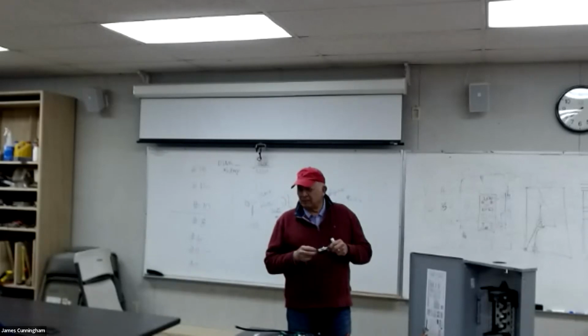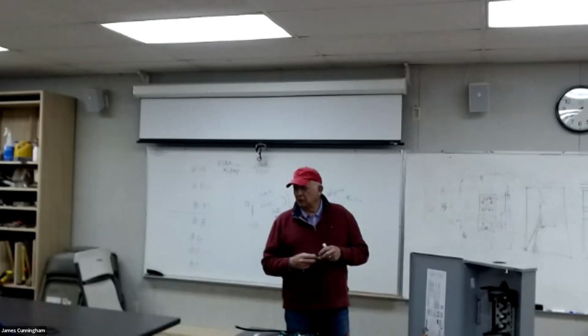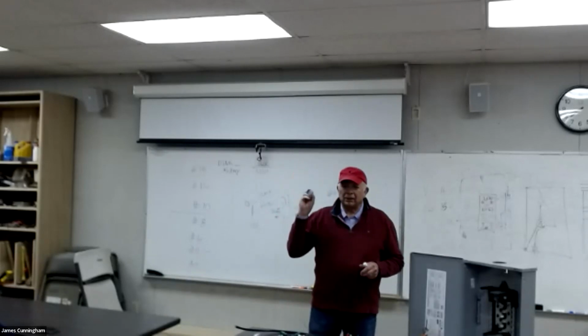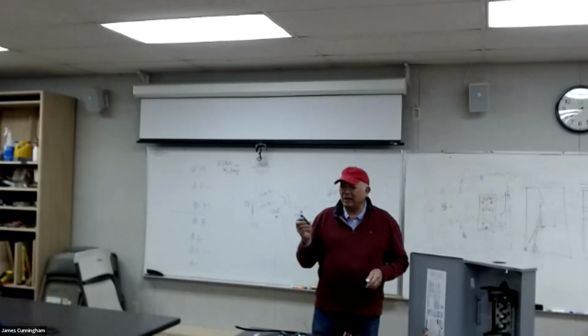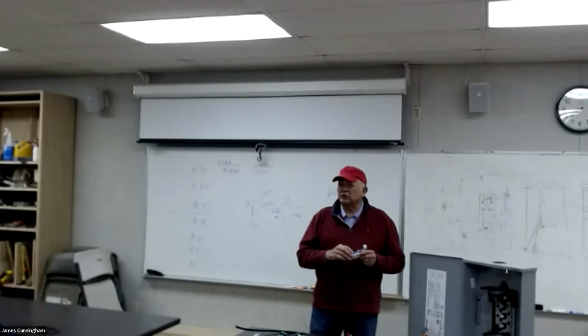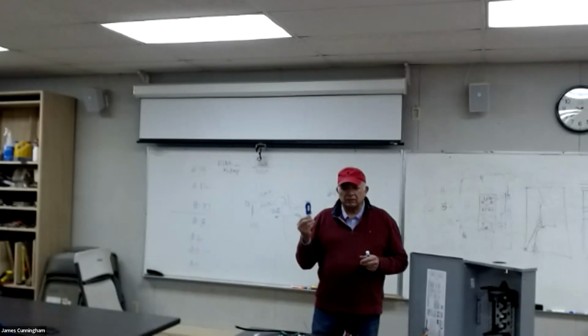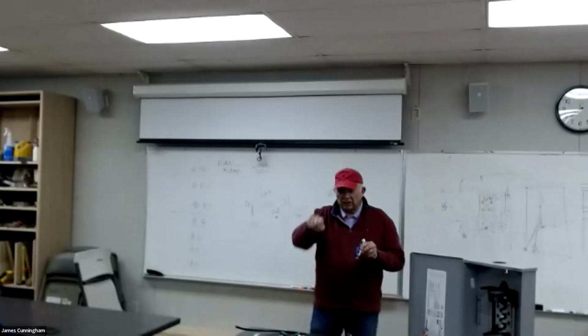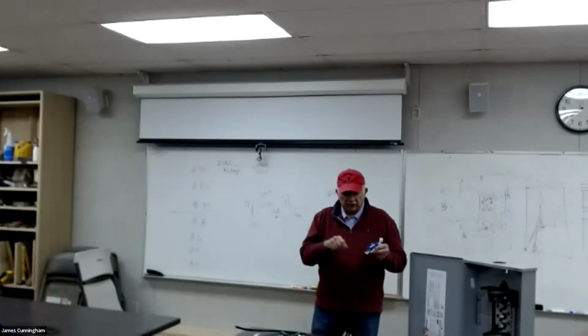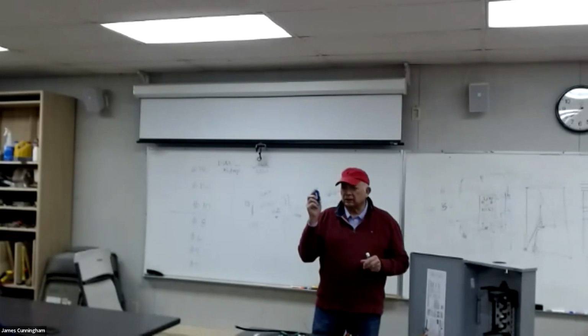If it's a plastic box, yes, you have to connect the grounding screw. On a plug, it doesn't matter. You have to connect the grounding screw no matter what. So whether it's a metal box or a plastic box, you have to connect the grounding wire. If it's a metal box, you have to connect the grounding wire to the metal box and then run a pigtail or extension of that wire to the grounding screw here.